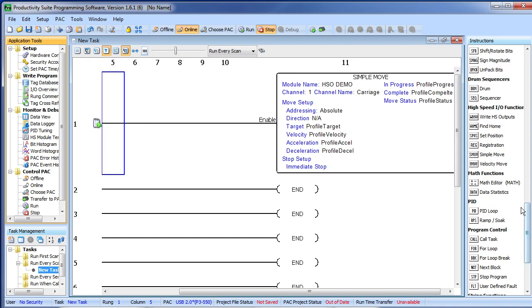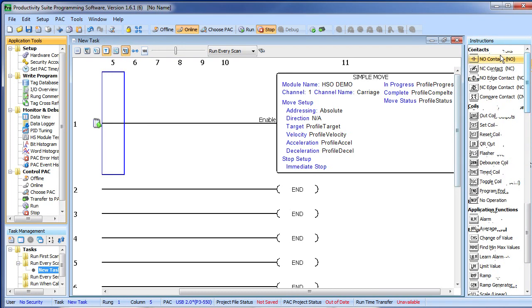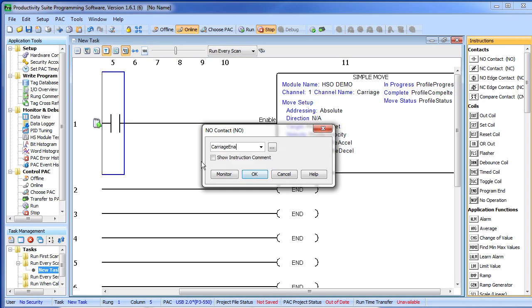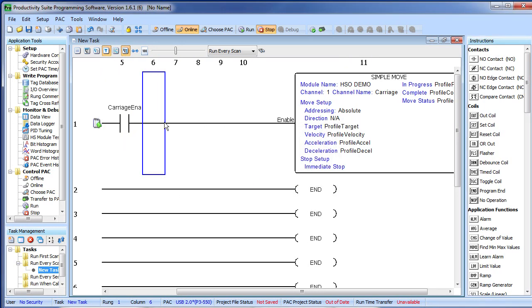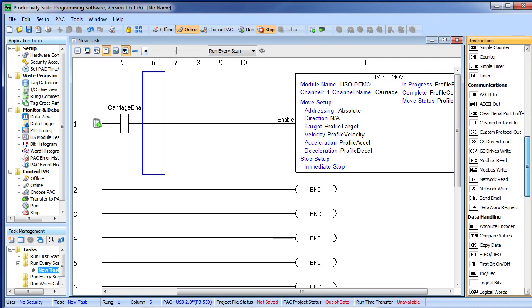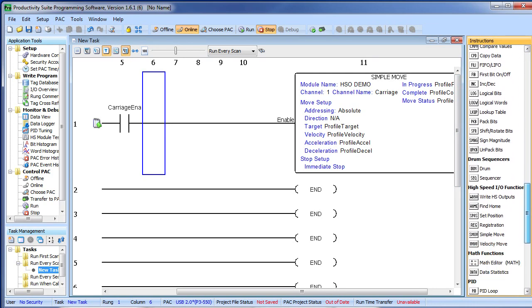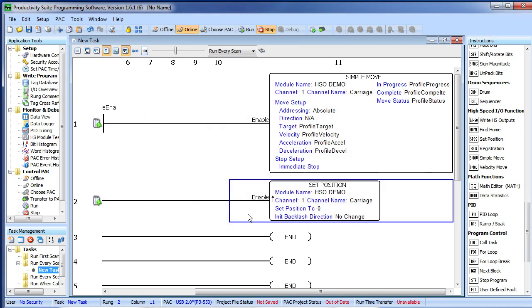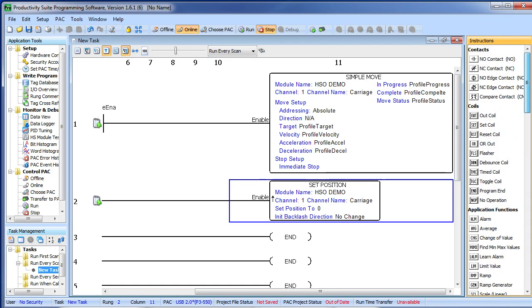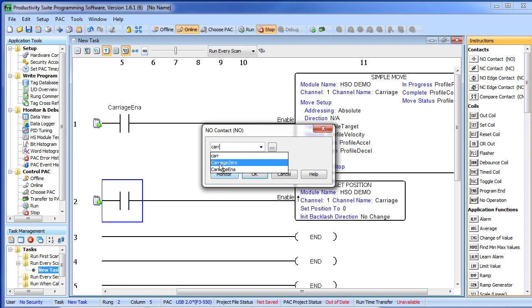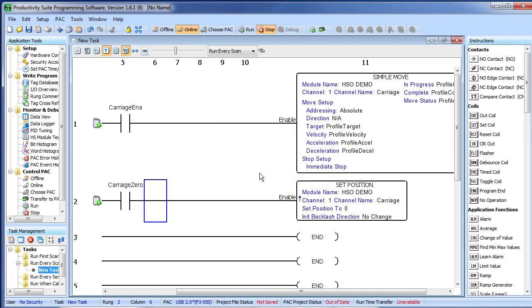So now if I go grab a contact, drop it in here, grab my enable and say OK, I now have a way of enabling this instruction. While we are at it, let's go ahead and set up our zero function. To do that I go back down to my high speed commands and I say set position. When this rung is enabled I want to set the position to zero. To enable that rung we go grab that other switch that we set up to zero things out. That's it, that's our whole program.